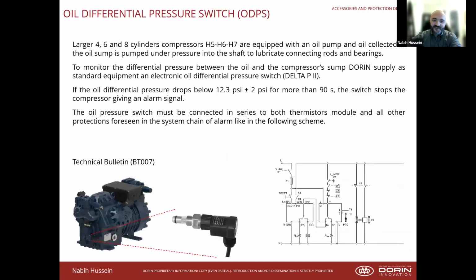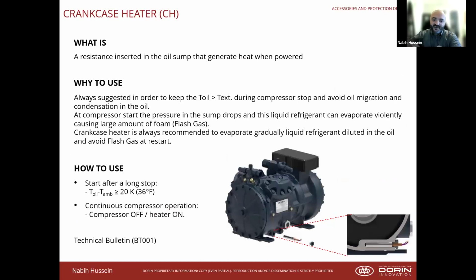And then the oil differential pressure switch, it's looking at about 12.3 psi plus or minus 2. If you remember from that graph you saw where the compressor kind of cut off, that's when the oil pressure fell below that 12.3 psi for longer than 90 seconds. Then the crankcase heater, we suggest this where compressors would spend a long time off, and then on startup, you have CO2 liquid inside the oil sump. So just before you do the startup, you heat up that oil sump to bubble out that liquid CO2.